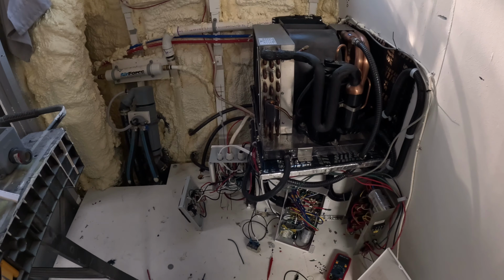This morning I came in. I didn't want the compressor running because that needs water flow and everything, and I couldn't do my testing. So I disconnected one of the power leads going to the compressor, then turned the system on, went in there, made sure it was on, ran the temperature way down low, and while I was in there I heard a click, so I said, well, I think the relay just tripped. Sure enough, I came out here, checked the ohmage on the contacts, and it was 0.